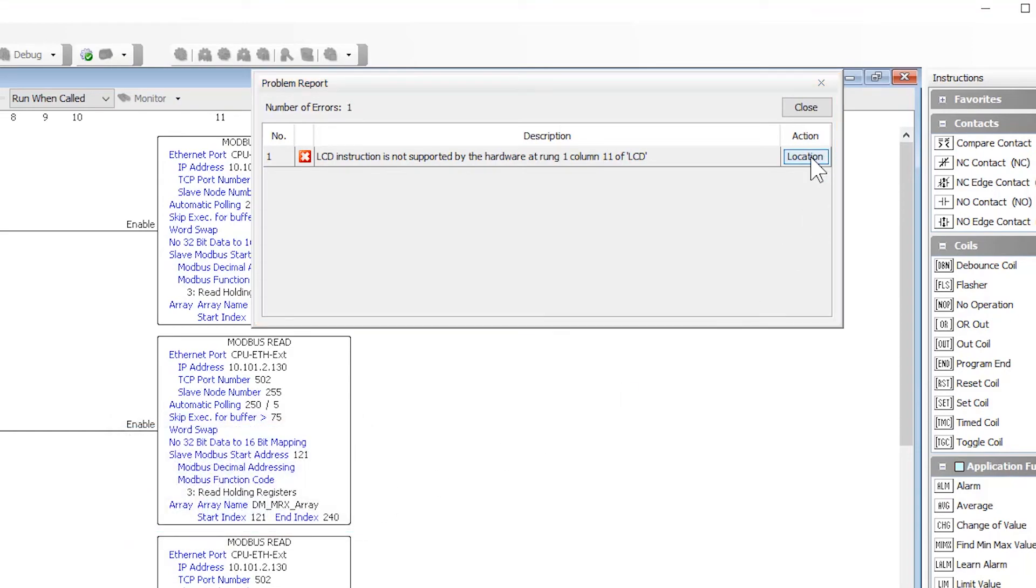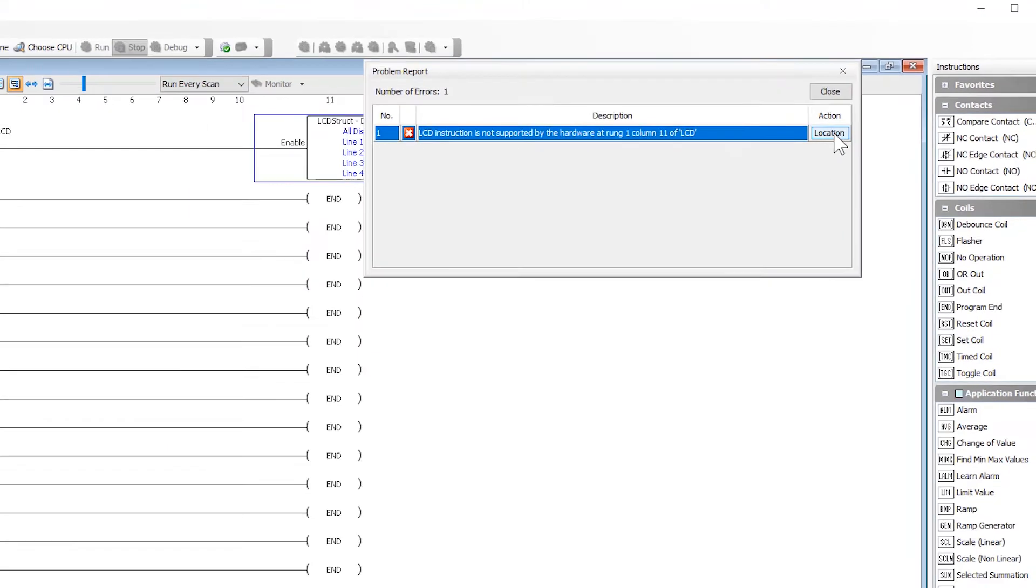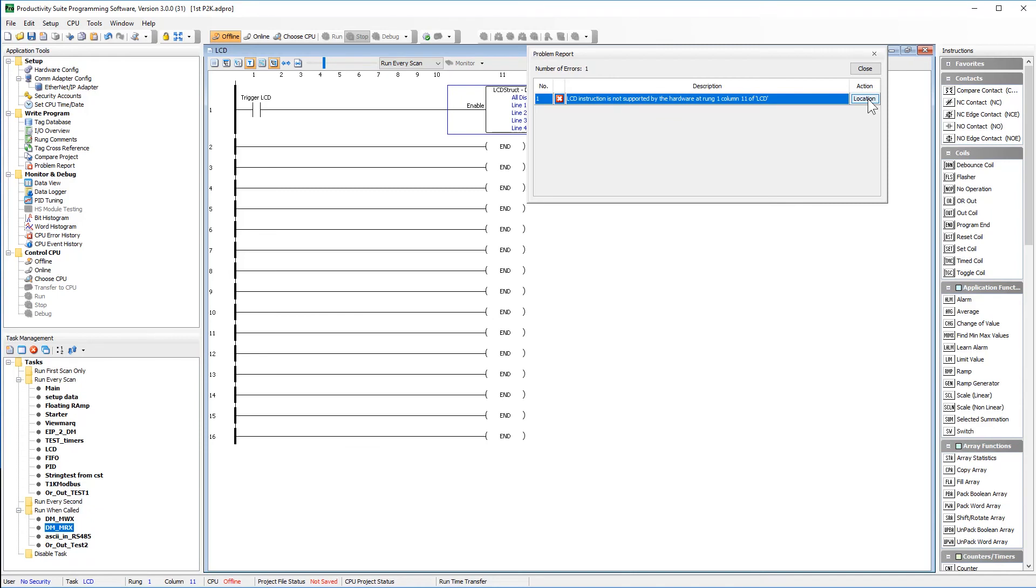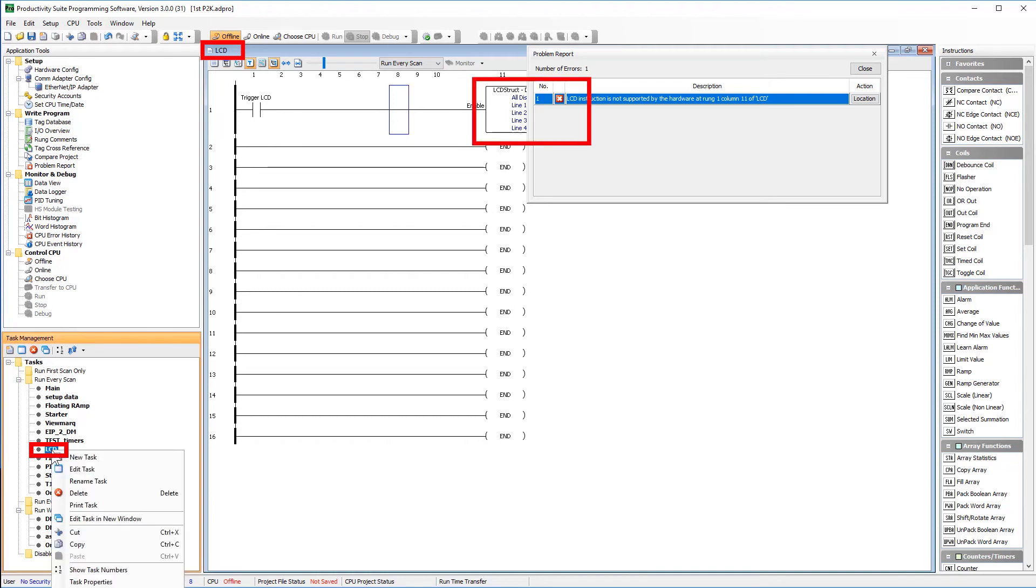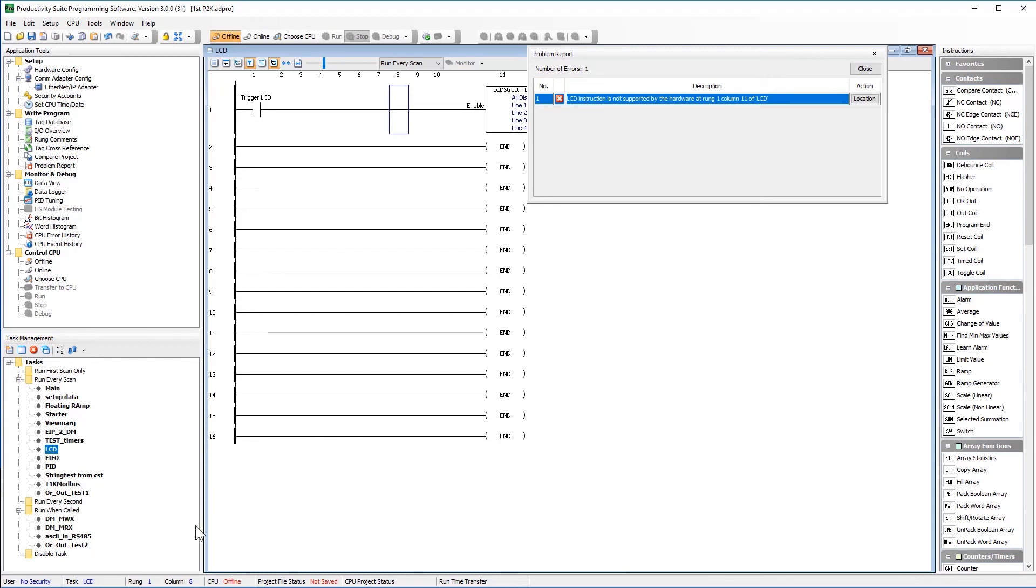Go ahead and hit this locate button and it will take you to the point of the error in your ladder code. Now I can see here that the only instruction in this task was this LCD instruction. I can delete the task or the instruction, or I can just take the whole task and move it down to the disabled task bin.